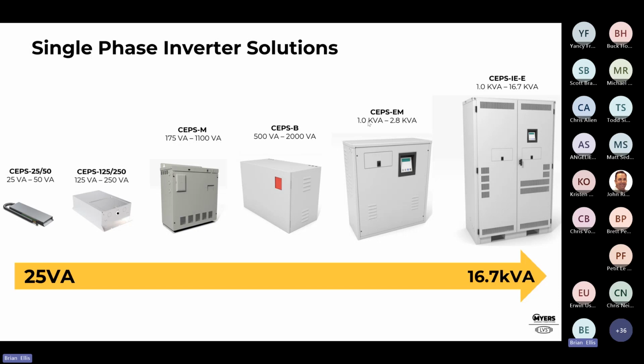Then we have the CEPS-EM, which is a 1 kVA up to 2.5 kVA. This is a smaller footprint, also allows you to have the bells and whistles that are available on the M, but it adds in the front meter panel. This comes standard with this product, whereas with the CEPS-M product, you have to add that if you want advanced testing and you want to monitor anything from the front meter panel.